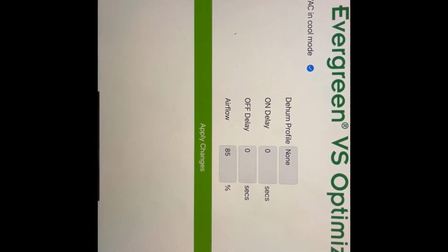So we're going to go ahead and turn the units on and both thermostats, because this is a zoning system, unfortunately. It's a single stage unit with zoning. No, I didn't design it, so don't blame me. Go ahead and take some flow hood measurements and see what we got for the total airflow, and then we can adjust plus or minus from there.